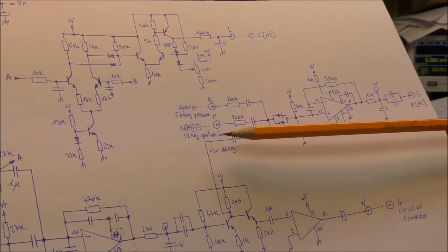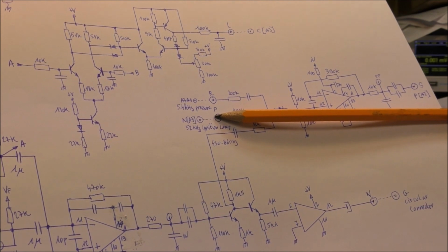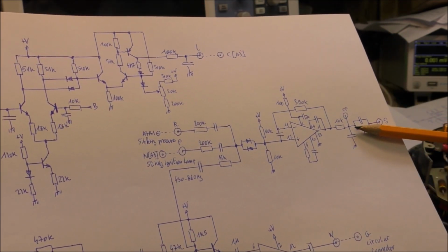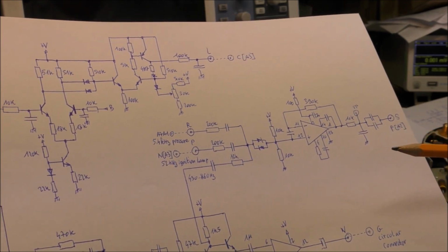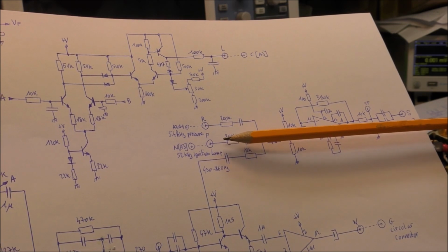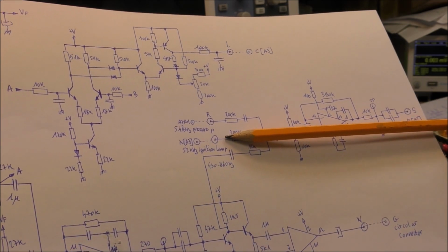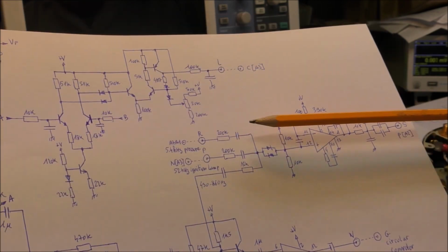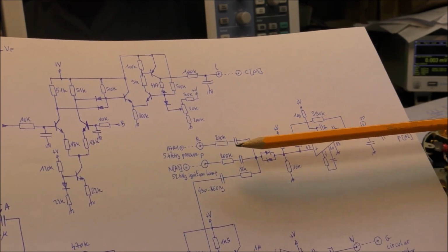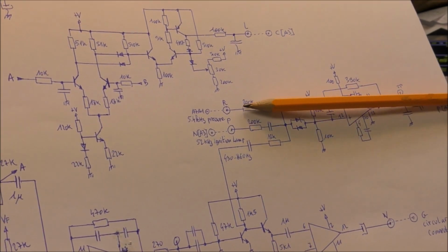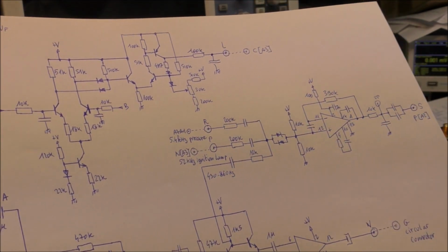On the second line, there is effectively the 52 kHz ignition lamp. So this permits the detection of a failure of that system. So normally, we should have a 52 kHz ignition signal at startup when the device is turned on. And after a while, the signal should disappear. And the third signal is a pressure signal we have seen on my previous video. So the signal is effectively around 5 kHz.